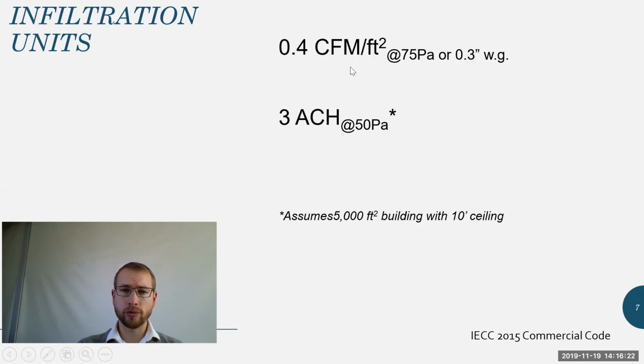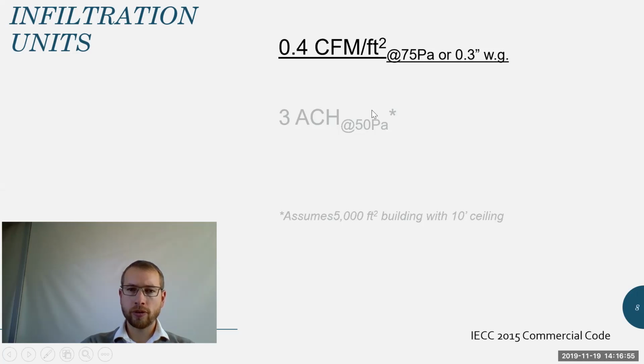Once again, IECC 2015, what we see in Idaho for commercial buildings. You want to keep your CFM per foot squared below 0.4 when the building is pressurized to 75 pascals, or 0.3 inches of water gauge. The 3 air changes per hour at 50 pascals is approximately equal to this, assuming a 5,000 square foot building with 10-foot ceilings, because the air change per hour really depends on the building volume. So generally, ignore the ACH and just stick with the CFM per foot squared.